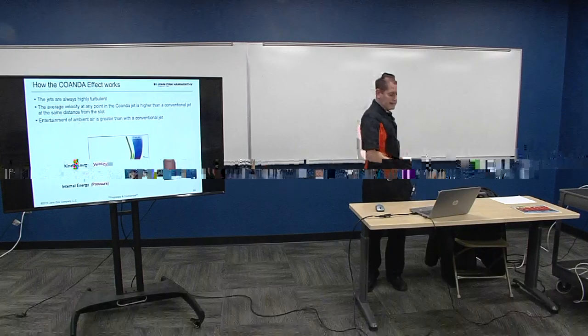So it's the Coanda effect, and we call them tulips, right? It's not their real name, but they look like a tulip, if you will, at the top. So there's a gas jet right here at the base of the tulip that forces that gas around that shape and directs it straight up instead of out. Now what that's doing is, again, low pressure zones are a lot about flare operation. When that gas film is pulled around, it creates a low pressure zone on this side here that sucks in air, right? So it creates a film that sucks in air and mixes right there on the tulip bowl, and that's what helps, again, with nice clean flames.